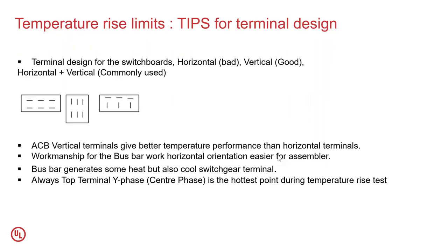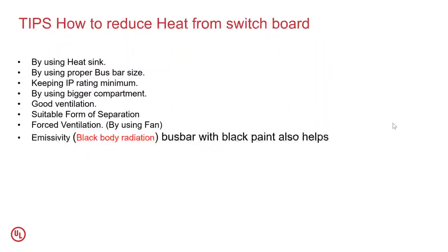Workmanship for the busbar is easier for horizontal orientation compared to vertical. But the advantage is with vertical orientation. The busbar generates some heat, but also cools the switchgear terminals. The busbar is very, very important, because it takes up heat from the terminals of the switchgear. Always keep this in mind. The top terminal, Y phase, nothing but the center phase, is the hottest point during the temperature rise test.